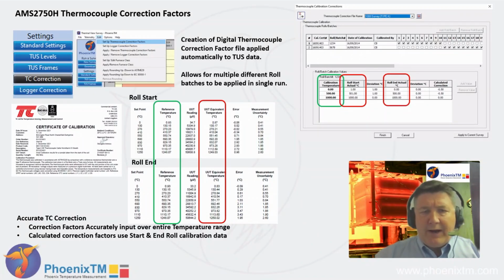Ensuring that the thermocouples are accurate is important, and having the necessary documentation and certification to back that up is essential. But an important part of the temperature uniformity survey is actually applying the information from the calibration for the thermocouple to allow you to perform what we call thermocouple correction for the test data itself. As we saw in a previous video, it's possible to create a correction factor file for the data logger. We can do the same thing for our thermocouples. Within the software, you can create a correction factor file for the thermocouples that are used for the survey. In the top right hand corner here, you can see the layout of the table, which looks very similar to the data logger correction factor file.